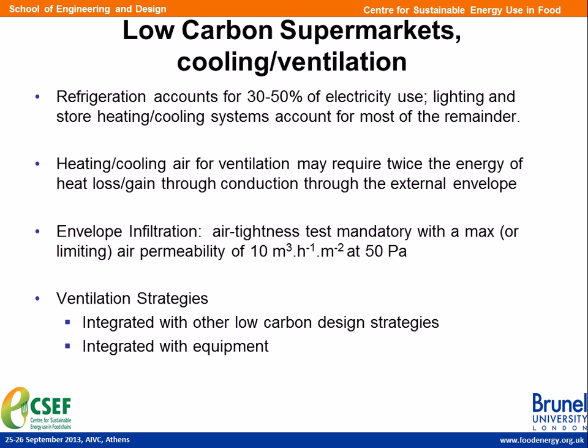For low carbon supermarkets, in the cooling and ventilation, in summary, refrigeration accounts for 30 to 50% of electricity use. Heating, cooling, and air for ventilation may require twice the energy of heat loss through conduction through the external envelope, which has been improved a lot during the last years. For envelope infiltration, air tightness tests are mandatory with a limit in air permeability of 10 cubic meters per hour per square meter at 50 pascals.